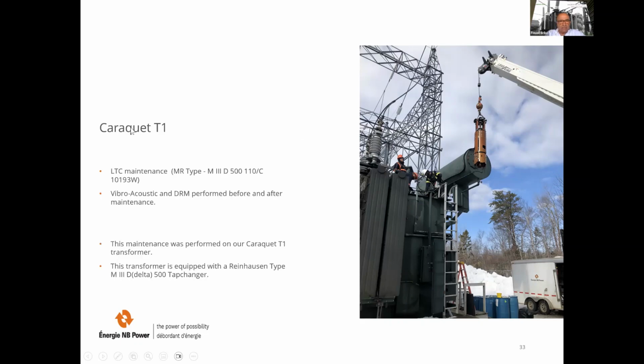The test was done in Caraquet. The name of the transformer was T1. It was an LTC maintenance, MR type, M3D500, with vibro-acoustic and DRM performed before and after maintenance. This maintenance was performed on the Caraquet T1 transformer, which is equipped with a Reinhausen type M3 Delta 500 tap changer. So please do not ask me detailed questions on this kind of tap changer.